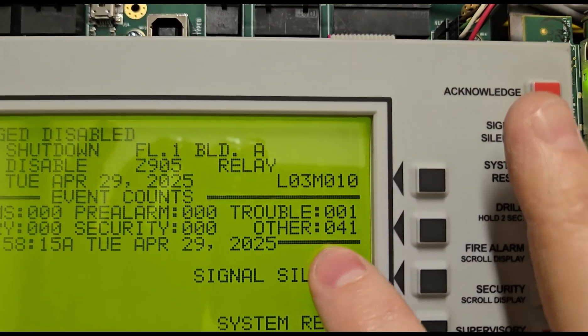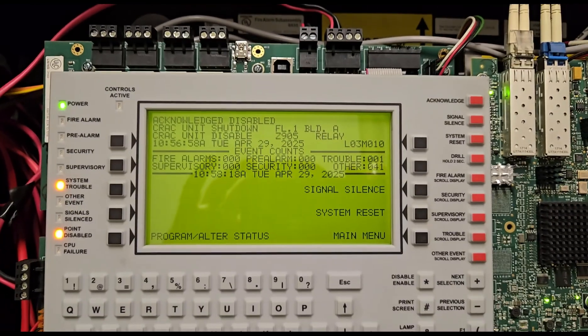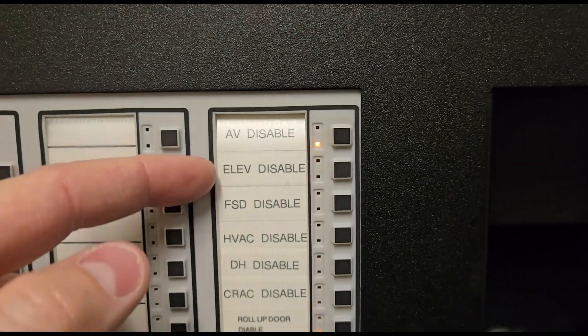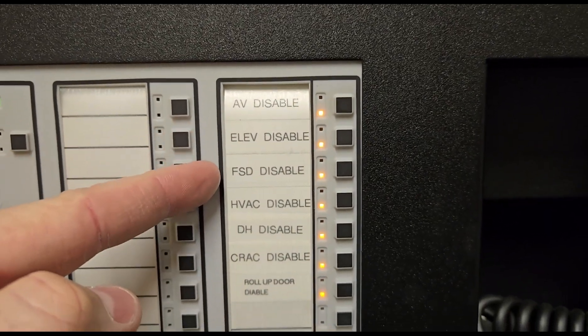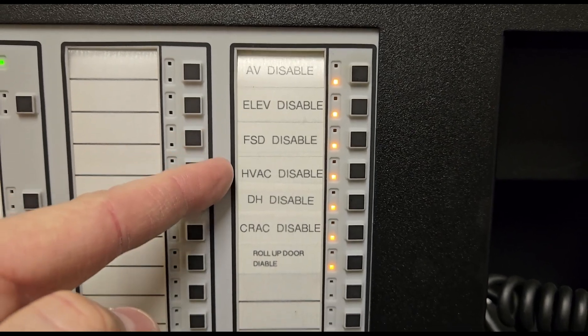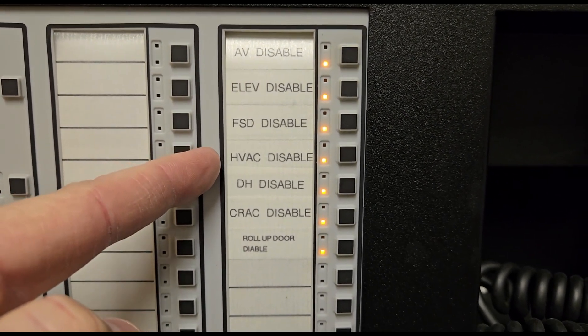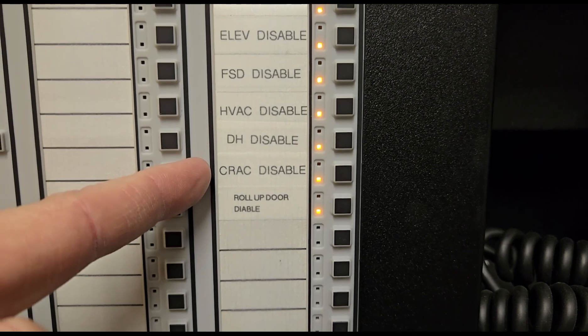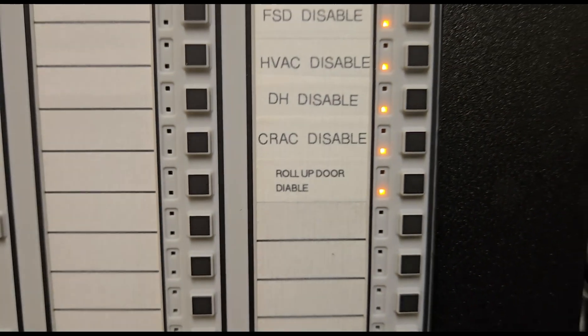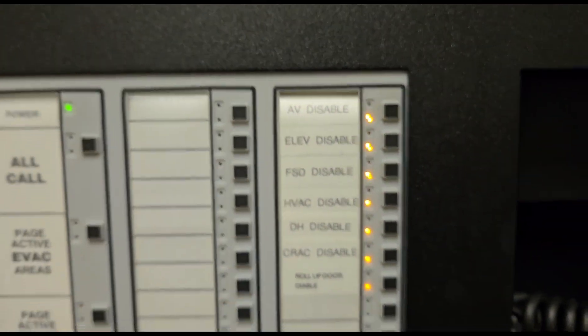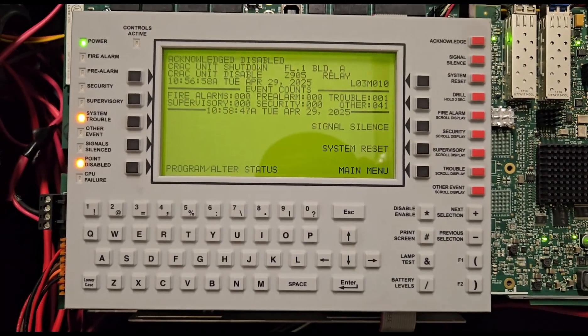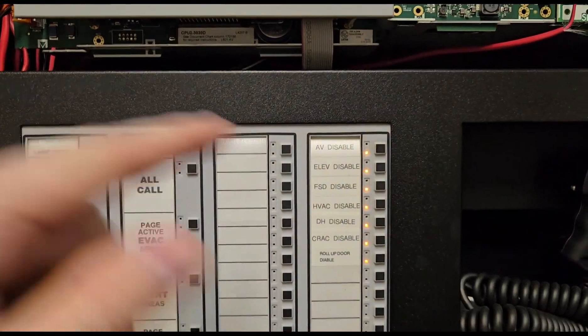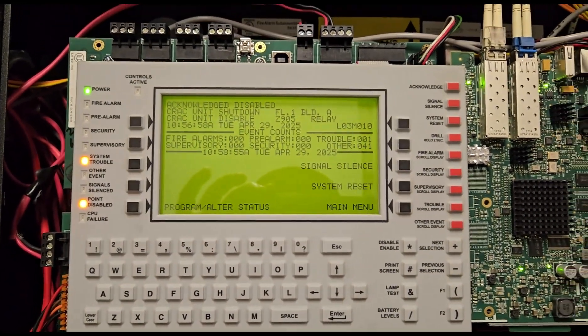There was originally one other signal, so I technically disabled 40 — the extra one is from the existing trouble on the panel. Now with all disabled points: no audibles will go off because AV is disabled; the elevator won't recall; none of the fire smoke dampers will close; the HVAC system will not shut down; none of the door holders will drop; none of the CRAC units will turn off; and the roll-up door will not fall.